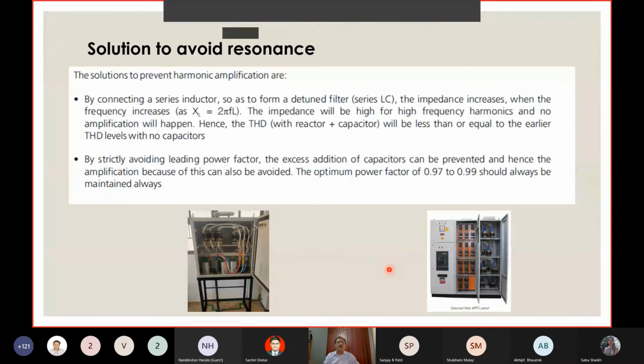So the capacitors in the circuit should not be plain. They should be used with the detuned reactors. So to avoid resonance, we need to have capacitors in series with the reactors, or you can have detuned APFC. When you say detuned APFC, you will have one compartment for reactors, one compartment in the behind is the capacitor, the contactors are here, and the main incomer is here. So 3-panel. This is what is recommended by most of the state chief electrical inspectors when it comes to detuned APFCs.